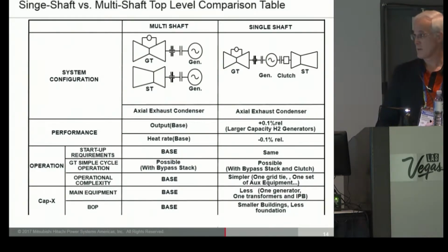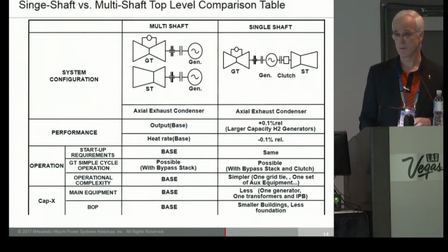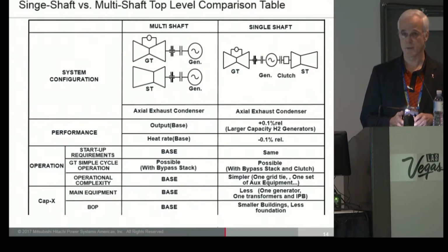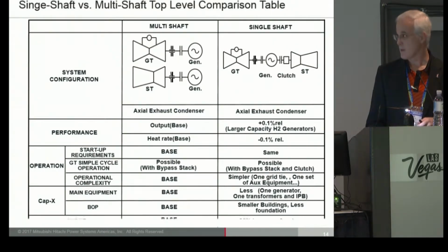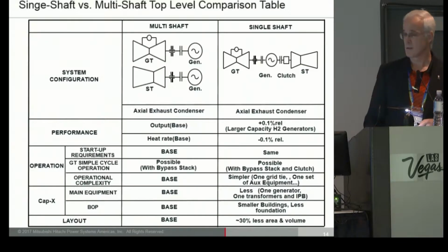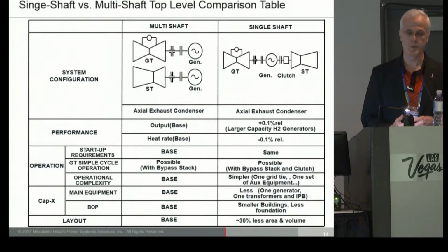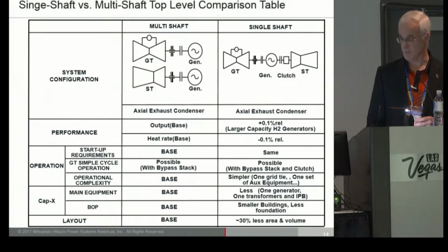Finally, as far as main equipment cost-wise, you've got one less generator, one less isophase bus, one less step-up transformer, so there's some savings there. Looking at buildings overall in the BOP, there are cost savings too: smaller building footprint, smaller building volume. As far as layout goes, there's about 30% savings in building area and volume between the two. So if you have to have a building, it's cheaper with a single shaft configuration.